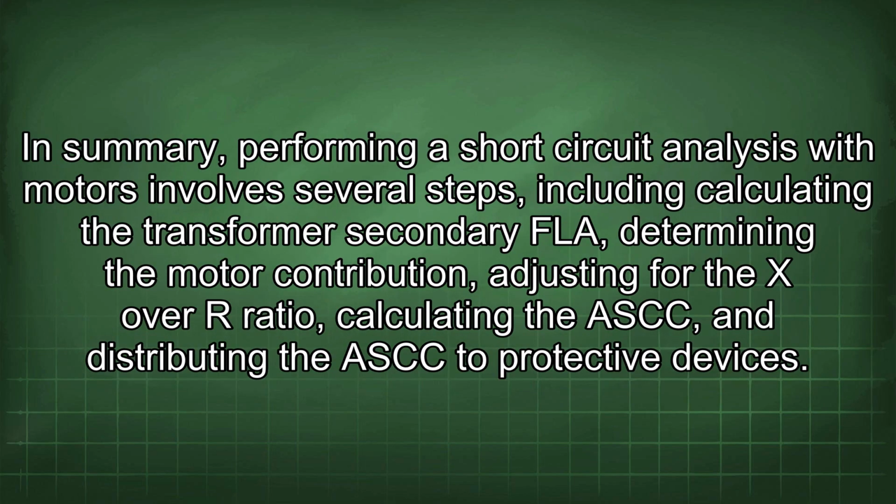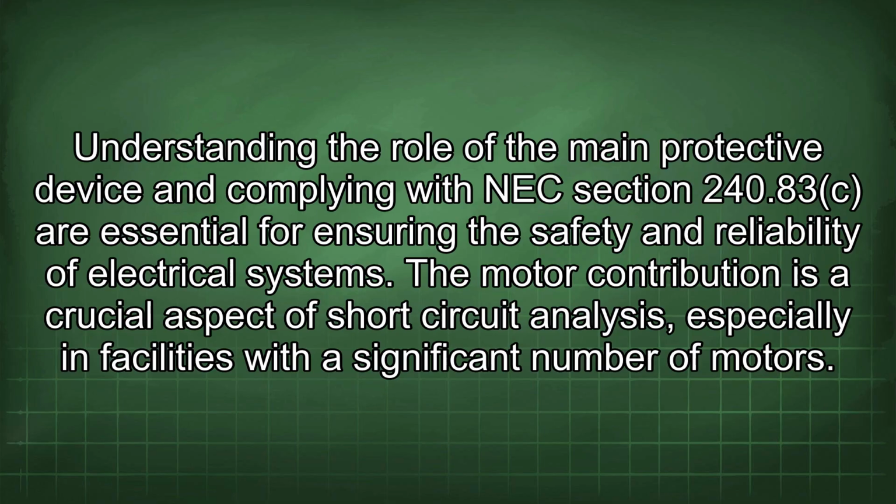In summary, performing a short-circuit analysis with motors involves several steps, including calculating the transformer secondary FLA, determining the motor contribution, adjusting for the X/R ratio, calculating the ASCC, and distributing the ASCC to protective devices. Understanding the role of the main protective device and complying with NEC Section 240.83 are essential for ensuring the safety and reliability of electrical systems.